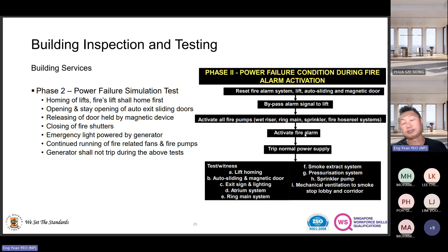Phase 3: so phase 1 we test fire alarm activation, phase 2 is power outage, and the third phase we test individual systems. We restore normal power, reset everything, bypass the lift so it can work, check the fire alarm panel, sub alarm panel, and all directional signs to see if they're lit up. Then we look at all the detectors.